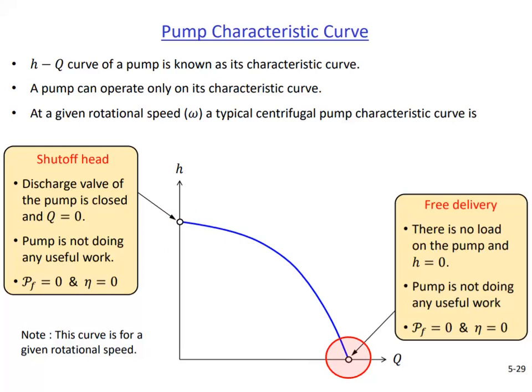Free delivery is the other extreme. Here the flow rate is maximized, but the generated head is zero. It is obtained when the discharge side of the pump is not connected to any piping system. In other words, there is no load on the pump. With zero head, no power is delivered to the fluid, and the efficiency is zero.